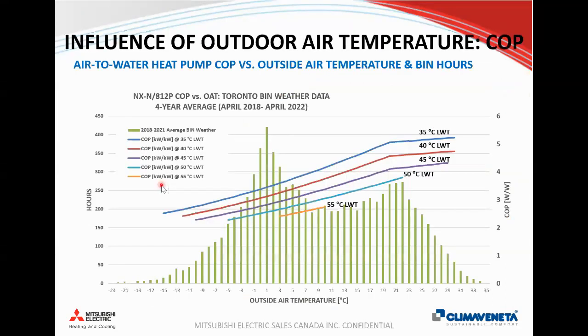So the last thing that will change is the COP, or the coefficient of performance. On the left-hand side of the axis, we have bin hours, and on the x-axis, we have our outside air temperature. There are 8,760 hours throughout the year. A bin hour distribution is just showing us how many hours we spend at 0 degrees, how many hours we spend around -1, and so forth.